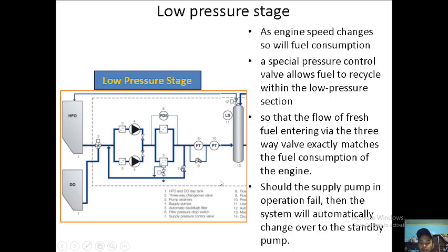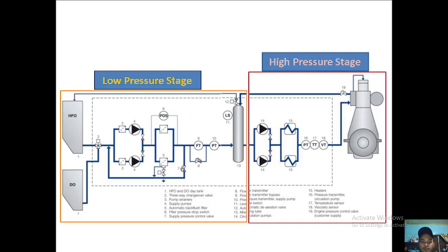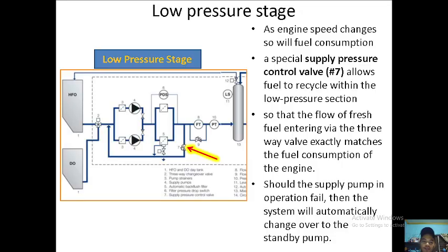Should the supply pump in operation fail, the system will automatically change over to the standby pump. So if this one is running and then it fails, the pressure transmitter detects a low pressure, and automatically the other pump on standby will start, so that it helps build up the pressure, to prevent pressure loss in the system that may cause stoppage of the engine. Okay, so that is more on the low pressure side. Now we will talk about the high pressure stage or side.